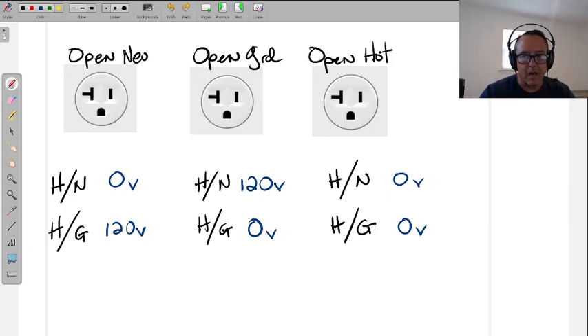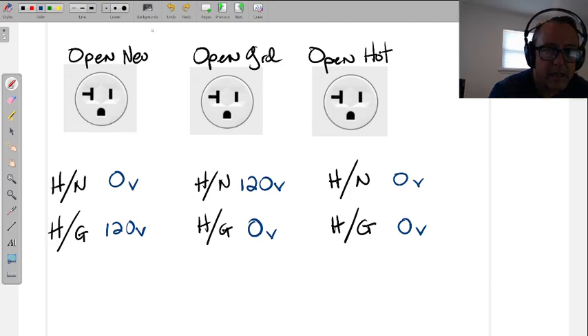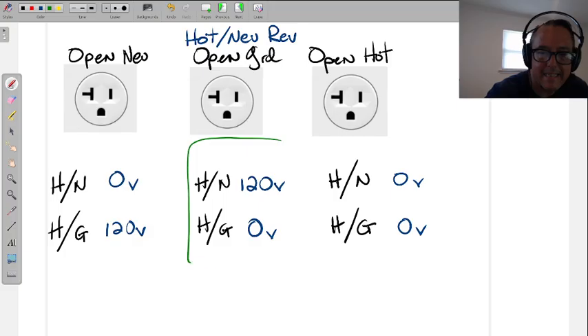So a lot of times the reversed hot and ground is not necessarily something that you're going to find or need to look for. The one that's more common and sometimes goes completely unnoticed is the hot neutral reversed. All right, and I'm actually going to put it here. Hot neutral reversed. And the reason I'm putting it there is because it looks exactly the same.